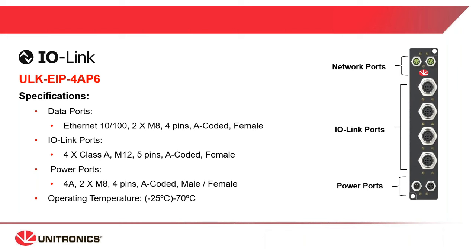A quick overview of the master specifications. For the four IO-Link port master, on the top you can see the Ethernet IP ports — we have two ports for daisy chain connection, in case you have more than one master on the machine or any other Ethernet IP device. Then you can see the four IO-Link class A ports, used for IO-Link devices such as sensors and actuators. On the bottom you can see the power ports, also with two ports for daisy chain connection. The operating temperature is minus 25 to plus 70 degrees, quite a big range.